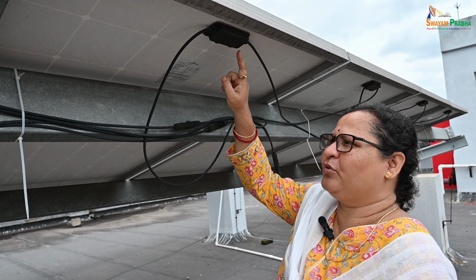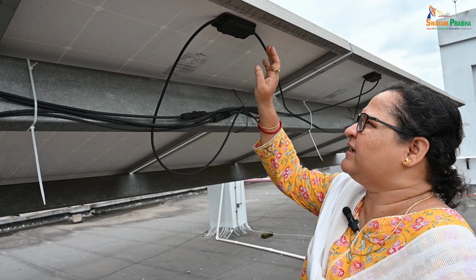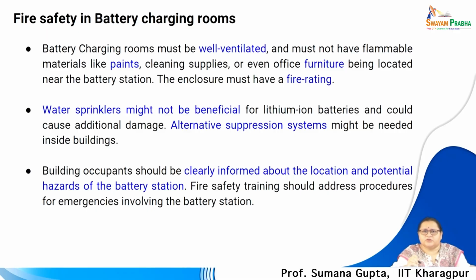A spark from this particular point can lead to a fire, and there are cases which have led to fire hazards. We have to be cautious on that. Also, in today's context, the battery charging rooms are coming in practice. If they are within the building or within the building basement, then these areas can become potential areas from where fire can spread. Water sprinkler might not be beneficial for lithium ion batteries.